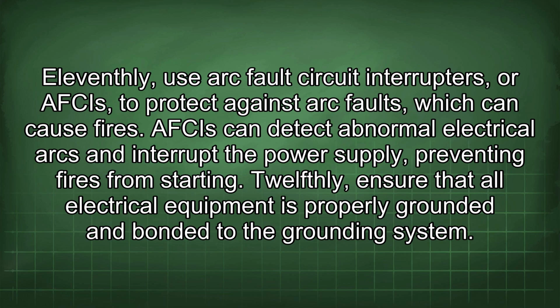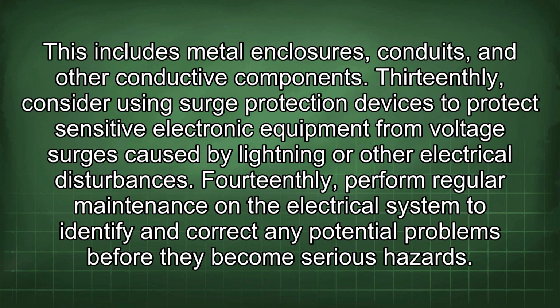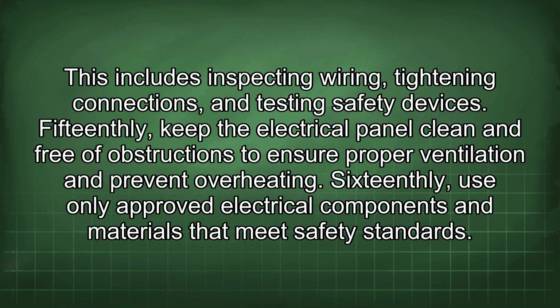12thly, ensure that all electrical equipment is properly grounded and bonded to the grounding system. This includes metal enclosures, conduits, and other conductive components. 13thly, consider using surge protection devices to protect sensitive electronic equipment from voltage surges caused by lightning or other electrical disturbances. 14thly, perform regular maintenance on the electrical system to identify and correct any potential problems before they become serious hazards. This includes inspecting wiring, tightening connections, and testing safety devices.